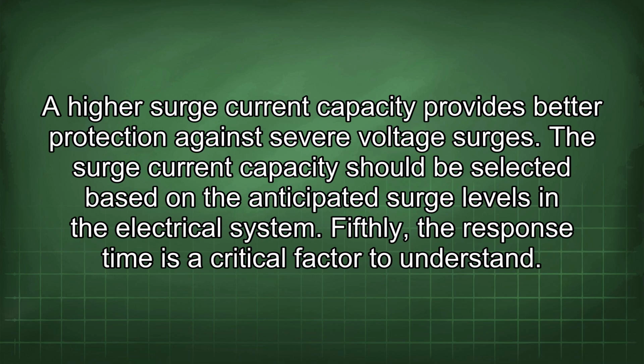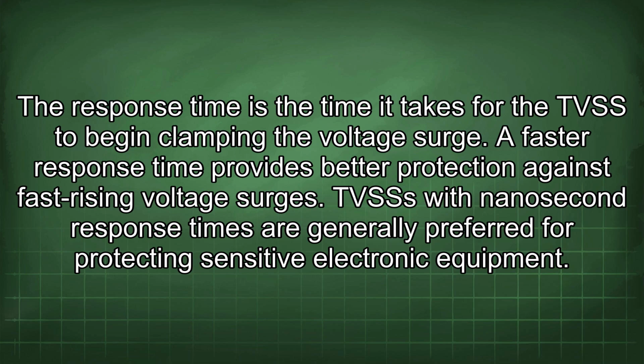Fifthly, the response time is a critical factor to understand. The response time is the time it takes for the TVSS to begin clamping the voltage surge. A faster response time provides better protection against fast rising voltage surges. TVSSs with nanosecond response times are generally preferred for protecting sensitive electronic equipment.